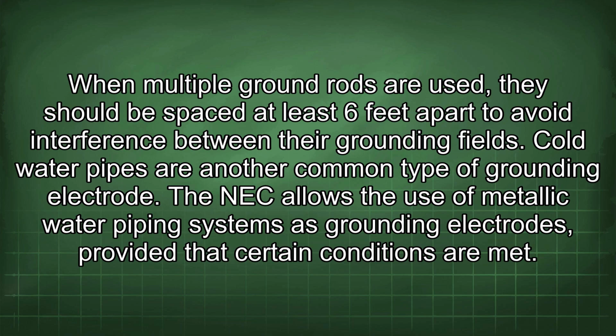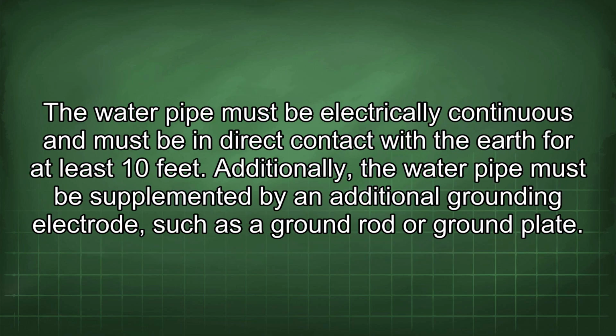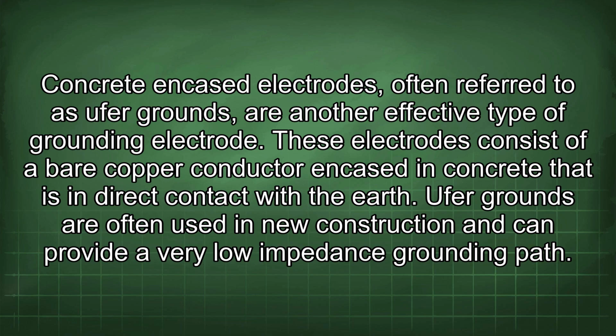The NEC allows the use of metallic water piping systems as grounding electrodes, provided that certain conditions are met. The water pipe must be electrically continuous and must be in direct contact with the earth for at least 10 feet. Additionally, the water pipe must be supplemented by an additional grounding electrode, such as a ground rod or ground plate. Concrete encased electrodes, often referred to as Ufer grounds, are another effective type of grounding electrode. These electrodes consist of a bare copper conductor encased in concrete that is in direct contact with the earth. Ufer grounds are often used in new construction and can provide a very low impedance grounding path.